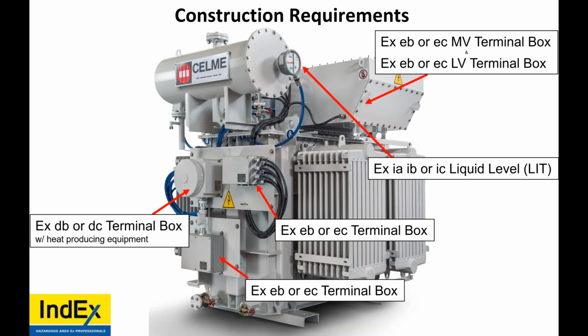What's the difference between IEC and NEC standards for classification of hazardous locations? Depends. IEC, you can follow zoning, or you can apply EPLs, which is a risk assessment. NEC, if you're going by classes and divs, is a much more restrictive method with less protection techniques available. So it's less flexible and more expensive. NEC 505, for classes and zones, is different than IEC. You cannot use IECEx equipment in America unless it has had specific electrical testing to their electrical standards, NFPA NEC 70.